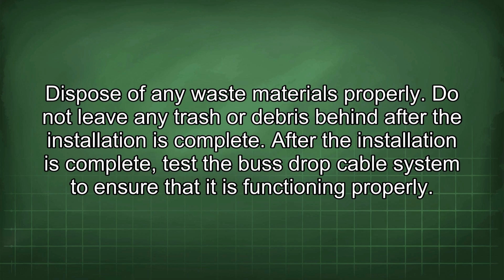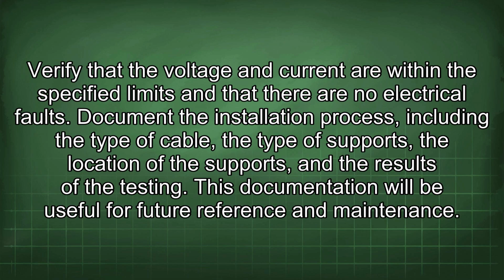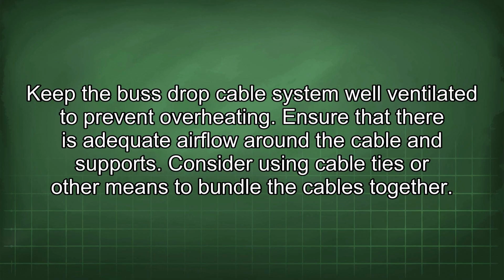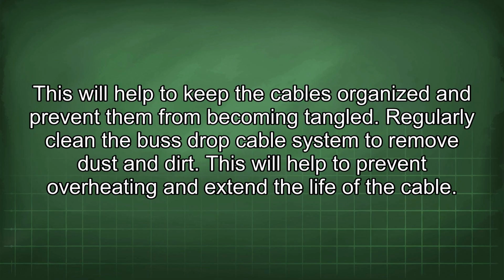After the installation is complete, test the bus drop cable system to ensure that it is functioning properly. Verify that the voltage and current are within the specified limits and that there are no electrical faults. Document the installation process, including the type of cable, the type of supports, the location of the supports, and the results of the testing. This documentation will be useful for future reference and maintenance. Keep the bus drop cable system well ventilated to prevent overheating. Ensure that there is adequate airflow around the cable and supports. Consider using cable ties or other means to bundle the cables together. This will help to keep the cables organized and prevent them from becoming tangled.